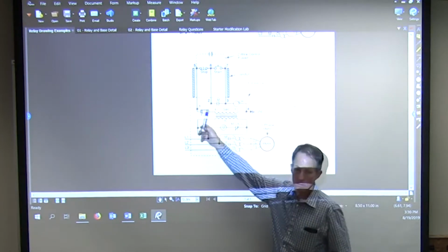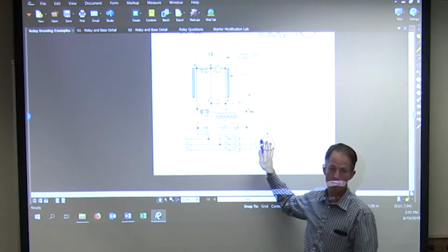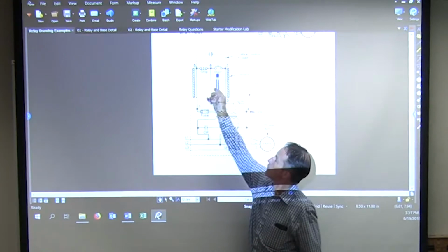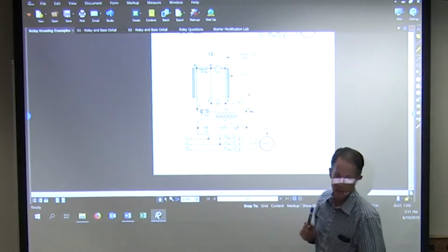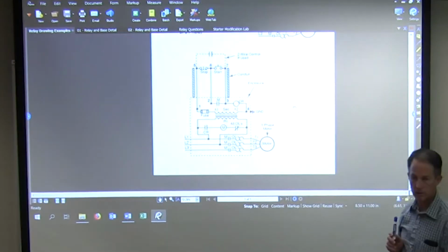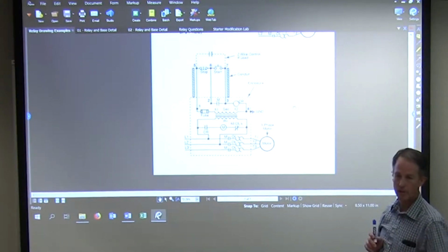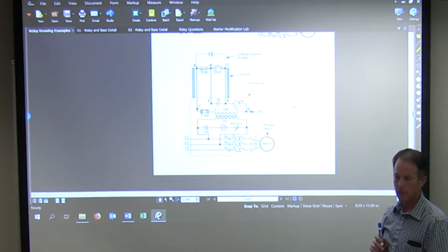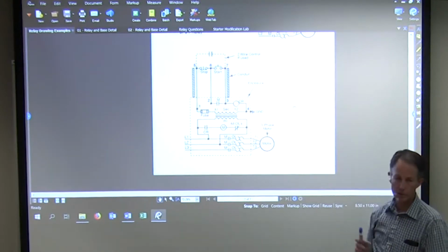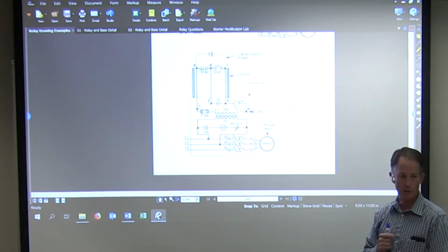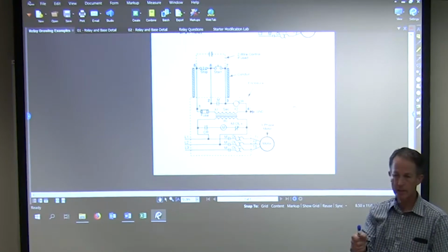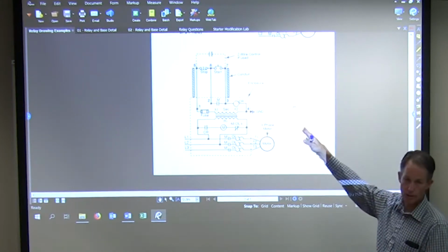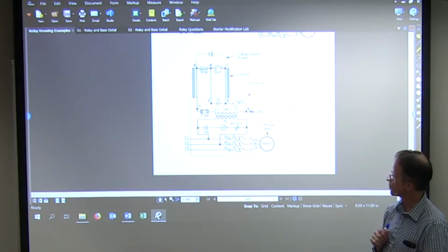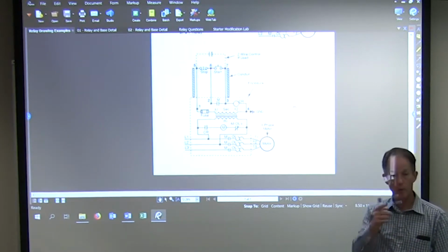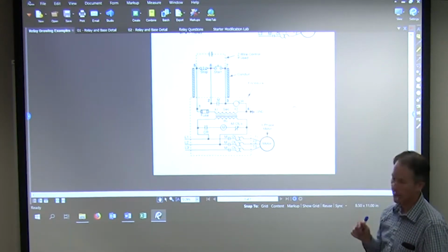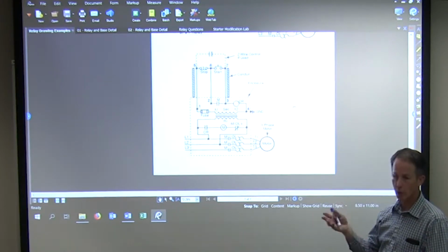So currently the motor's off. I have 2 buttons up here, right? The stop button is normally what? Closed. And is it momentary or holding? Momentary. Okay, these symbols are typically the symbol for a momentary push button. I press the button and it switches from its drawn state to the opposite state. So the stop is a momentary, normally closed. And what's the start? Momentary, normally open.